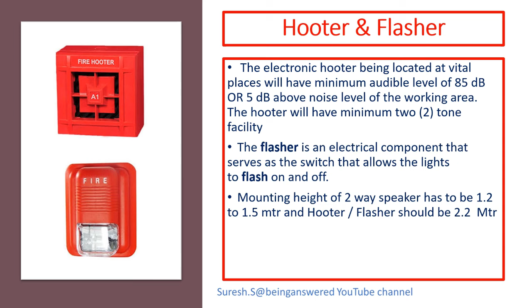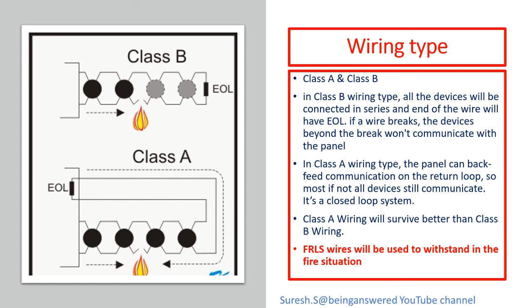There are two types of wiring method in the fire alarm system, class A and class B. In class B wiring type, all the devices will be connected in series and the end of the wire will have an EOL. If the wire breaks, the devices beyond the break won't communicate with the panel. In class A wiring type, the panel can backfeed communication on the return loop. So most, if not all, devices still communicate. It is a closed loop system. Class A wiring will survive better than class B wiring. FRLS wires will be used to withstand the fire situation. Class A and class B drawing will give you a clear understanding about the difference between the wiring.